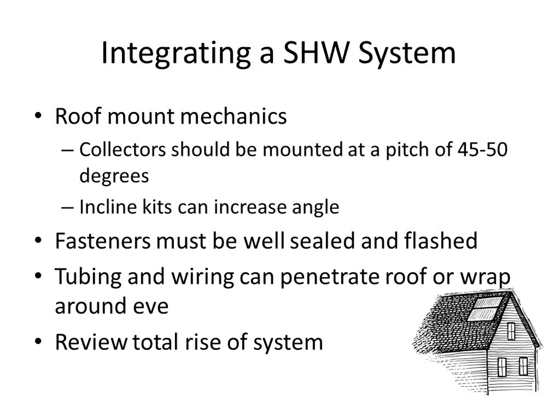You need to make sure the system that you're looking at is rated to handle a glycol rise of that level. And where you really ought to look at that is if you're looking at larger diameter piping going up to the roof, and you get into the 1/2 or 3/4 inch diameter piping, the glycol weight begins to become significant, particularly if it's a drain back system. And you need an oversized pump to get the glycol up to the roof. When you're looking at systems with very, very narrow tubing, particularly if they're closed, generally speaking, they're not going to limit the height of the collector from the heat exchanger.